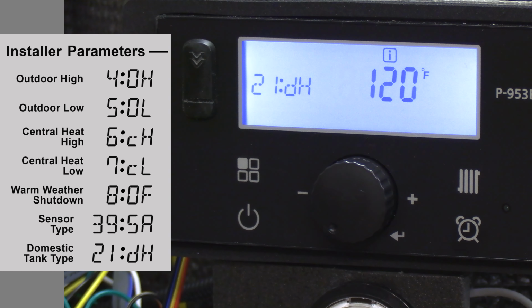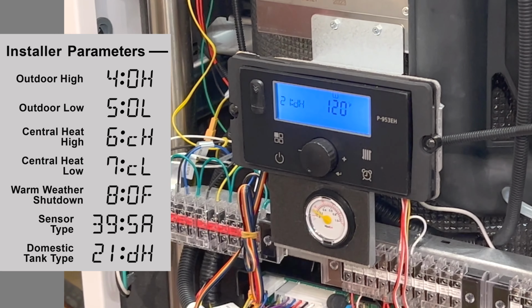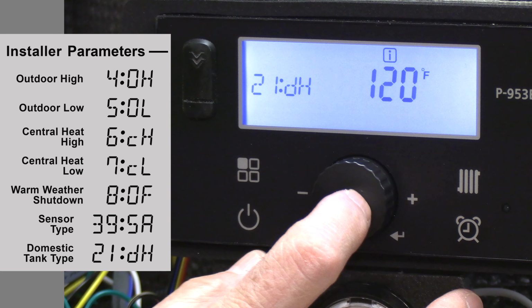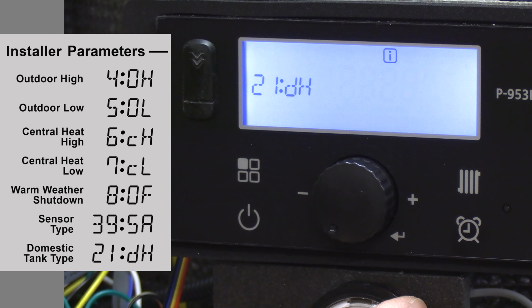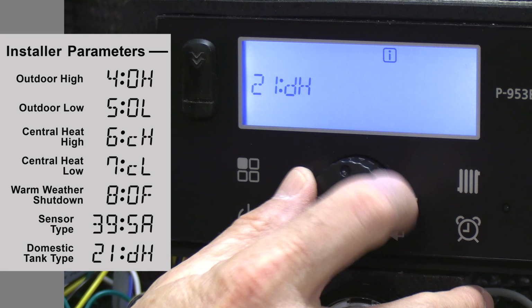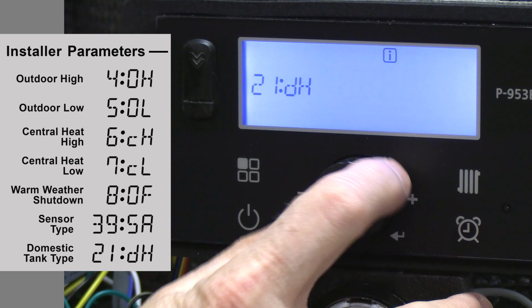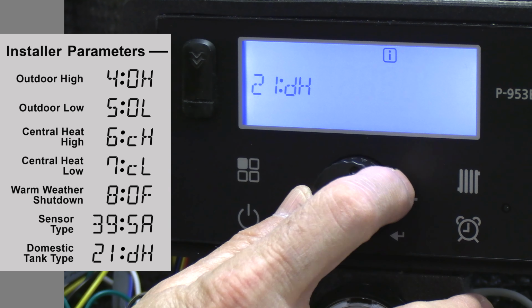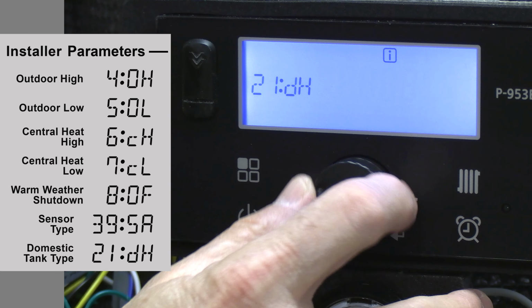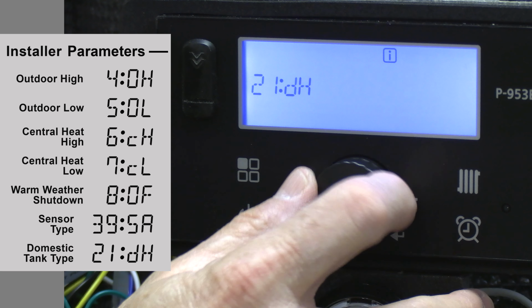So what are we using? Are we using a mechanical aquastat, or are we using an NTC sensor? Keep in mind, if I'm using an aquastat and my aquastat is set for 120, I want hotter water leaving the heater to overcome that temperature. So it's an indirect tank, right? So I'm going to press the scroll select button, and I'm going to jack that up to 180. Why? Because we want hotter water for that indirect coil. That way we can satisfy that domestic demand quickly.